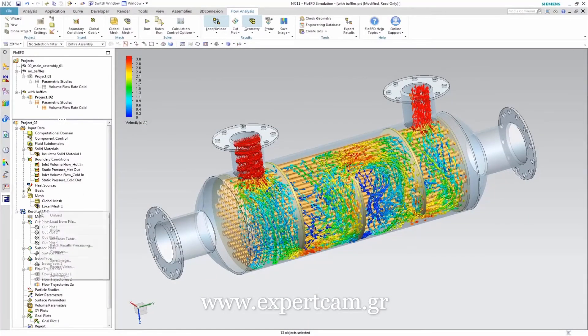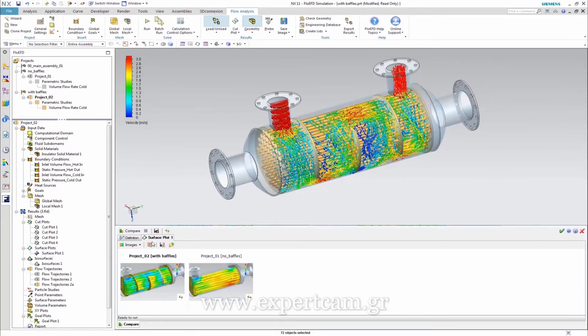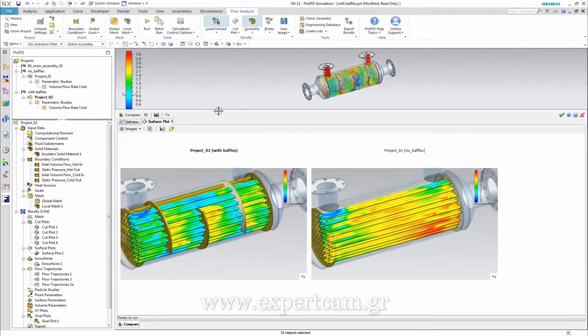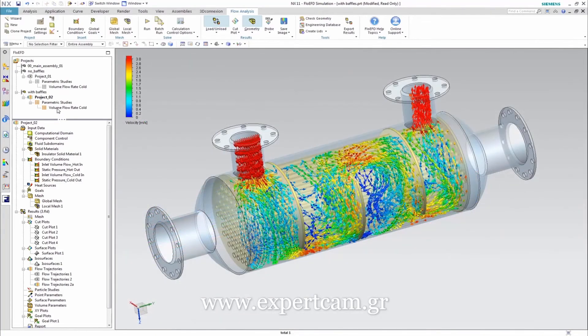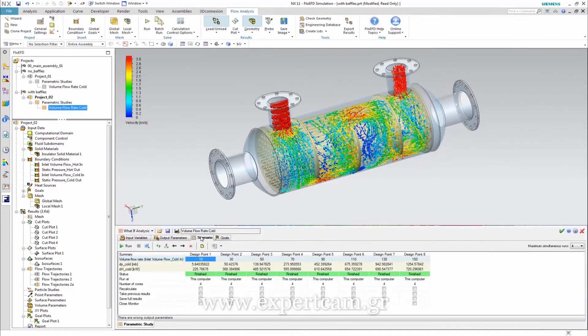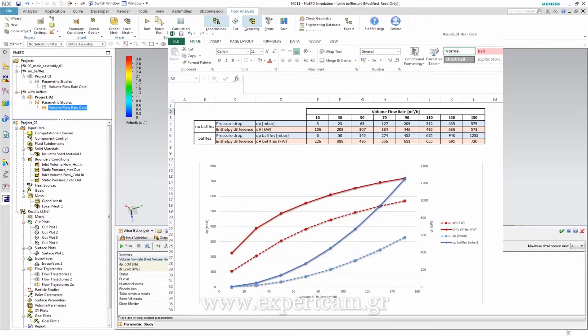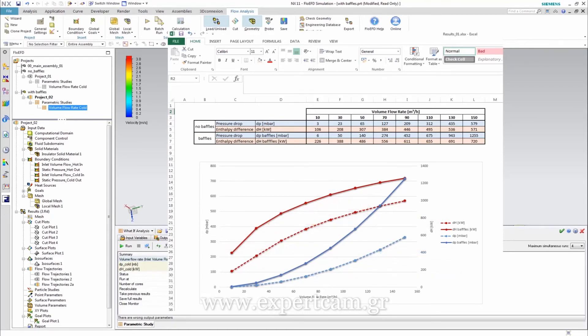The compare tool allows us to compare the results simultaneously. Let's look at the solid temperature on the tube surfaces, which seems to be more uniform for the version equipped with the baffles. Looking at the parametric study again, we can compare the results of the two variants. The solid lines show the variant equipped with the baffles, the dashed lines show the variant without the baffles. We can see that the variant with baffles has a higher thermal output, but also a higher pressure drop at the same time.